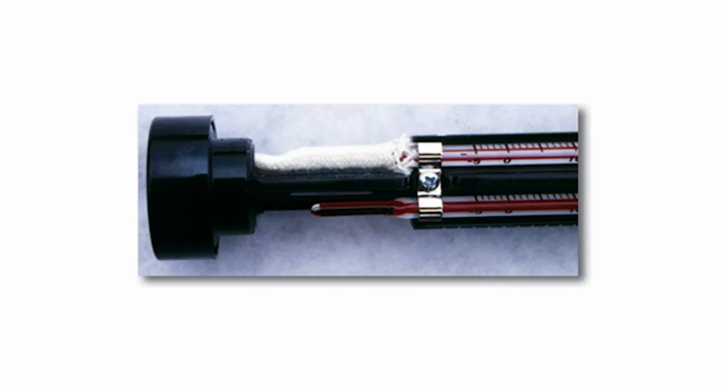So how is the whirling psychrometer used? Basically, it consists of two thermometers. One's called a dry bulb, one's called a wet bulb. The dry bulb is measuring the air temperature, and the wet bulb is used to determine the latent heat loss by whirling the instrument through the air until the dry bulb and wet bulb stabilize. And then the relative humidity and dew point are determined using basically psychrometric charts or lookup tables based on the air temperature and actually the delta or the difference between the stable dry bulb and the stable wet bulb measurement.